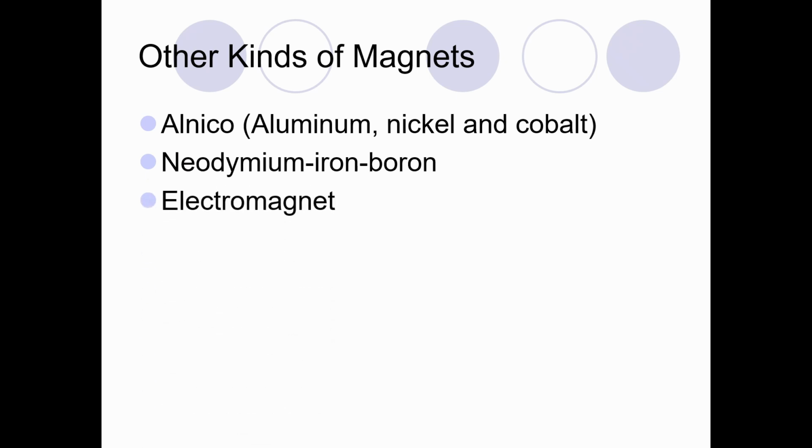The important characteristic of an electromagnet is that it can be turned on or off using a switch. The push-button locks that secure the position of your X-ray tube during an exam are electromagnets. MR scanners are electromagnets with a difference. The electrical current is introduced in the coils, and it circulates endlessly in the coils because they are supercooled with liquid helium to the point where resistance in the coil is near 0.